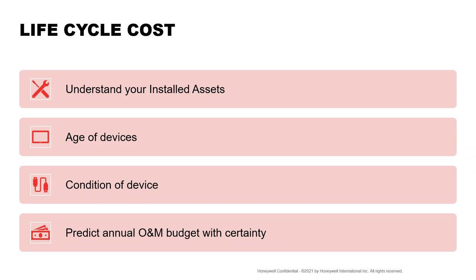So do you know what devices and assets are connected to the fire system as an end user? Well, you do now. Do you know when the devices were installed? Do you know what the manufacturer's recommended lifespan of the devices are? Well, with the systems that we're putting out there now, yes, you do. What is the condition of the devices, and are we having too many unwanted alarms from any particular units? That can be seen and monitored much more easily, and that history is right there. So when the service guy goes in to look after the system, he's pre-armed with a lot of information about what that system's doing before he just rocks up at the site and then drags all that out of the memory on the fire panel.